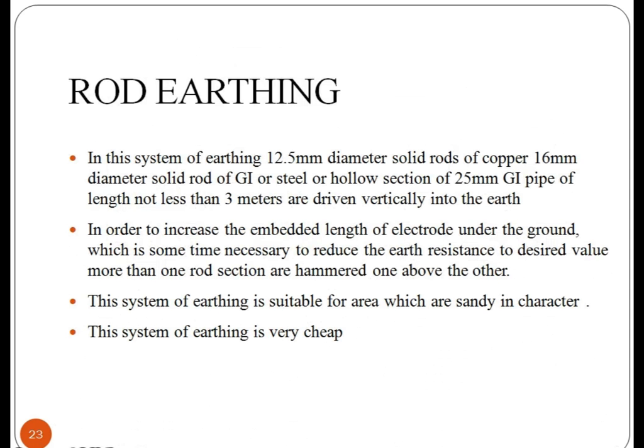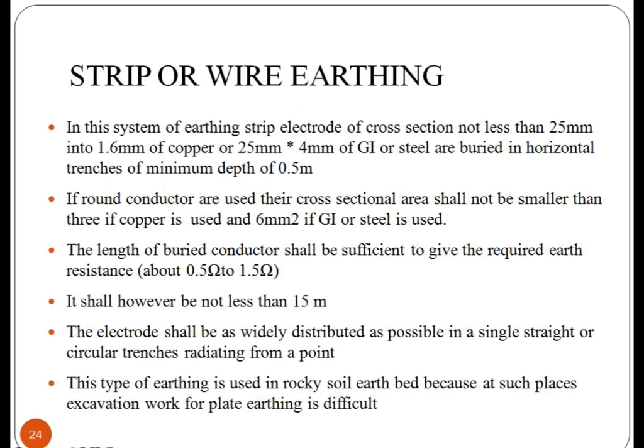Rod earthing. It is a type of earthing used to increase the embedded length of the electrode under the ground and to reduce the earth resistance to the desired value using more than one rod section. This system of earthing is very cheap and suitable for areas which are sandy in character. In strip earthing, which is also called wire earthing, the electrode cross section is not less than 25 mm by 1.6 mm of copper or 25 mm by 4 mm of GI. The length of buried conductor shall be sufficient to give the required earth resistance and is distributed as widely as possible in single straight or circular trenches radiating from a point.